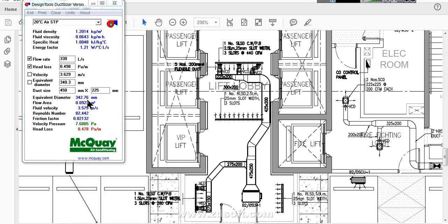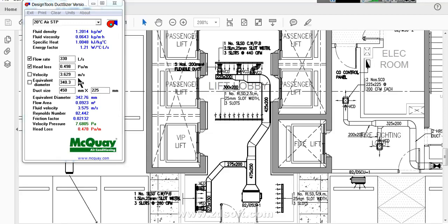There are two methods to calculate duct sizing. One is equal velocity system and equal friction loss system. Normally all the engineering consultants will do the equal friction loss method.